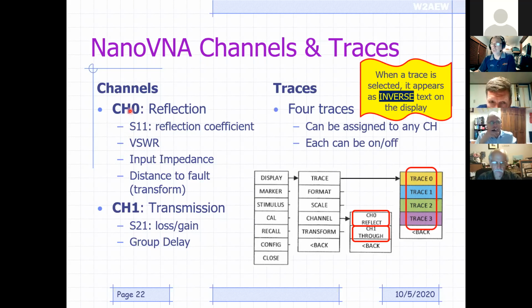Okay. So the traces, you can have up to 4 traces, and those traces can be assigned to any of the channels. So if I bring up display and go to trace, I've got trace 1, 2, 3, and 4. And then you pick one of those traces, and then you can tell it which channel you want that trace to be on. Okay. So whether you want that trace to measure a reflection property or a transmission property. Okay. And that's what the menu structure looks like to do it.